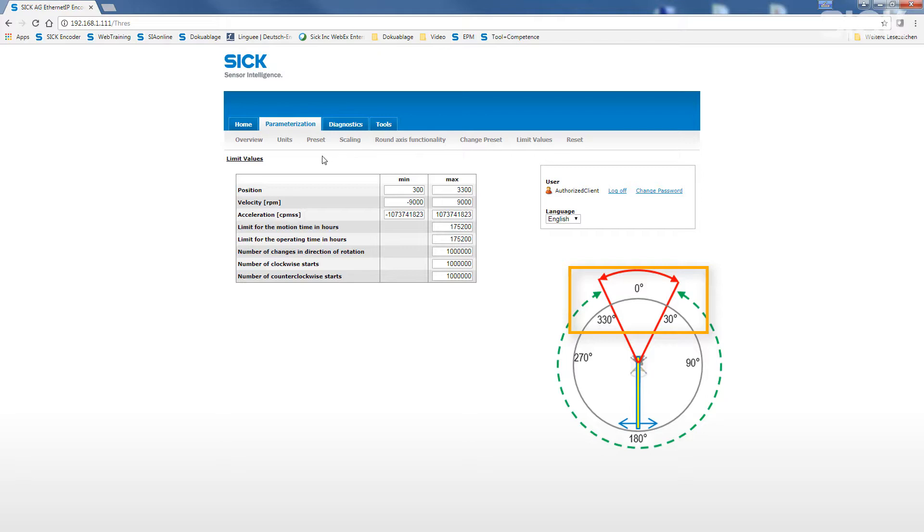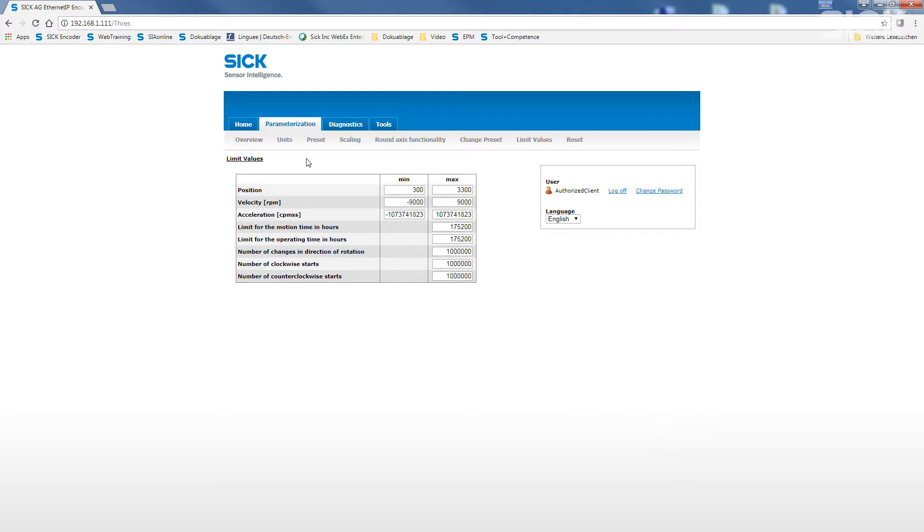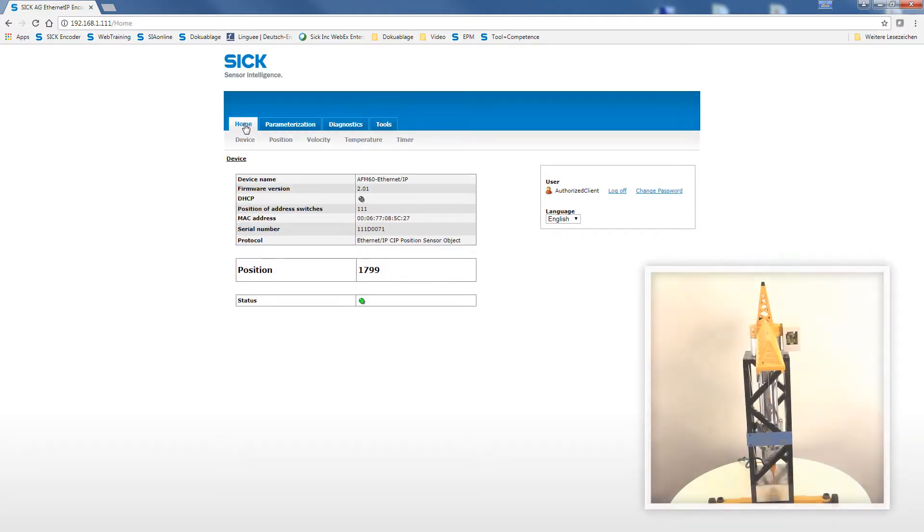We enter 300 for the minimum position and 3300 for the maximum position value. A dropping below or exceeding of one of these limit values will automatically lead to a status warning signal. Let's see how this works out when starting our application.